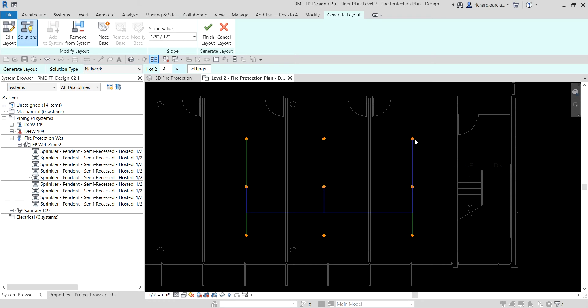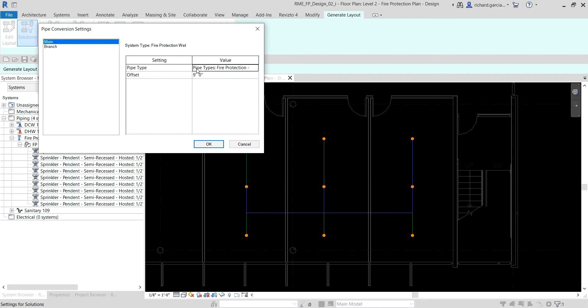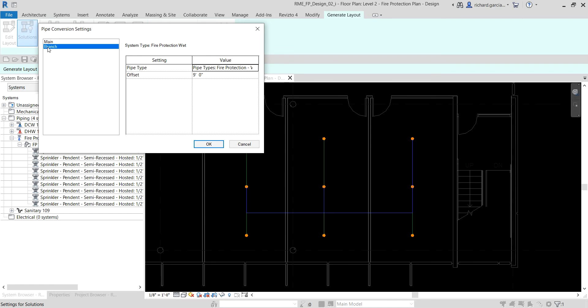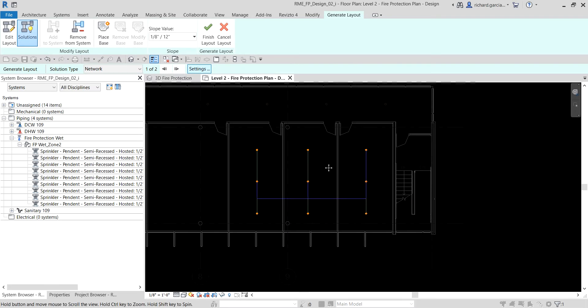Before selecting a solution, let's check the settings. Under Main Pipe, the pipe type is Fire Protection Wet and the offset is nine feet, which places the pipe main at nine feet above Level 2. For the Branch, the branch offset allows you to automatically create branches that run above or below the main and other obstacles. I'll make sure the branch offset is also nine feet with the same pipe type, Fire Protection Wet, then click OK.